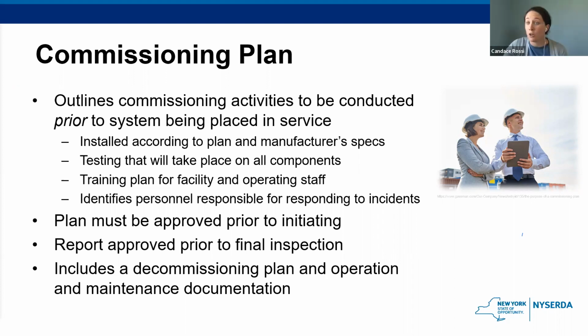So they need to provide all of that as part of the commissioning plan, and this plan needs to be approved prior to the start of commissioning. And then a commissioning report is also required that describes the results of commissioning and will be provided to the fire code official prior to the final inspection and approval. So there is definitely a bunch of requirements for these energy storage systems up front to ensure that they're being installed as safely as possible.